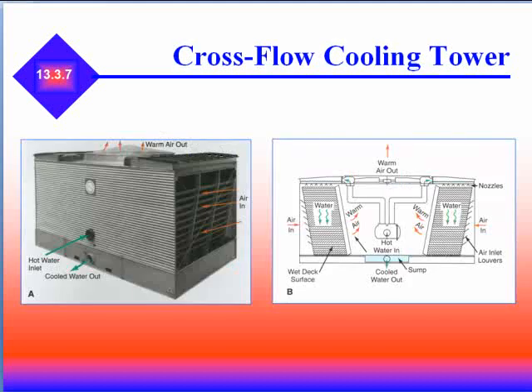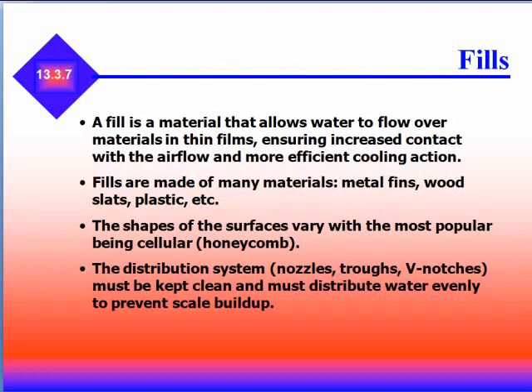This is an example of a cross flow cooling tower — hot water inlet, cooled water outlet, and the water flows across the decks. A fill is a material that allows water to flow over surfaces in thin films, ensuring increased contact with airflow and more efficient cooling action. Fills are made of many materials — metal fins, wood slats, plastic, etc. The shapes of the fill surfaces vary, with the most popular being cellular or honeycomb.